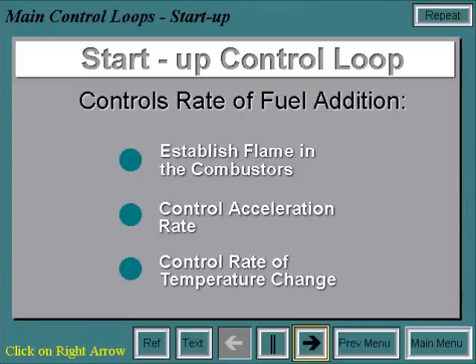The start-up control loop controls the rate of fuel addition for several reasons: to establish flame in the combustors, to control the acceleration rate, and to control the rate of temperature change.